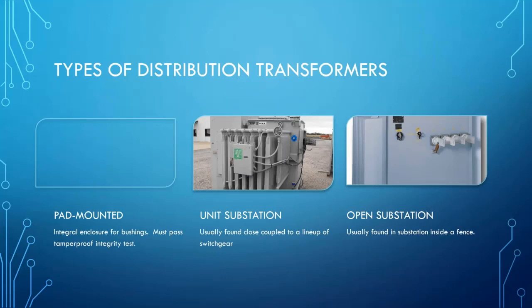And so there are three types of distribution transformers. There are pad mounted transformers. Looks like the picture didn't make it into that slide. The interesting thing about pad mounted transformers is, and I can't quote the ANSI standard from memory right now, but pad mounted transformers must pass what we call an enclosure integrity test. So they must be tamper proof. So once you specify that the transformer is a pad mounted unit, now you have forced a manufacturer to adhere to certain standards to make sure that transformer is tamper-proof. So if it went onto a college campus or a public area, the possibility is very, very slim that someone could get into that transformer and be harmed by the voltage.